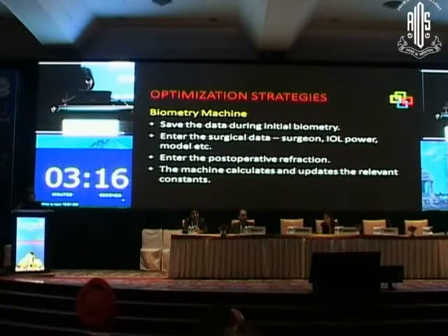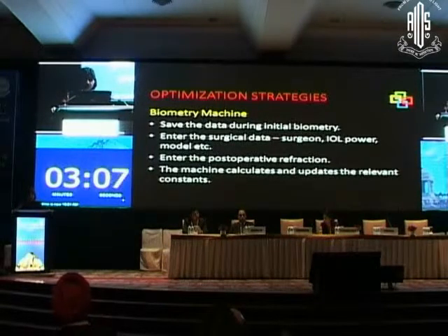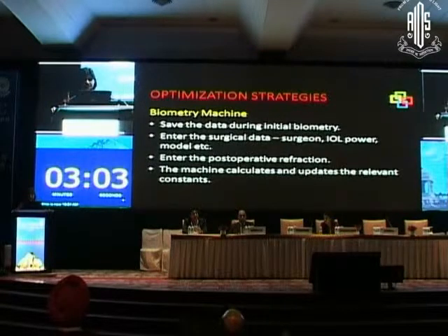Okay, but there is a limitation of the biometry machine also. For one, it is a little bit cumbersome to enter the data in. And more importantly, it has a memory issue. At least the older machines did not have too much memory, so sometimes you could not enter more than 100 cases. And we want to put in as many cases as we want, because the more good data we put in, the better our results will become. They will keep becoming better.